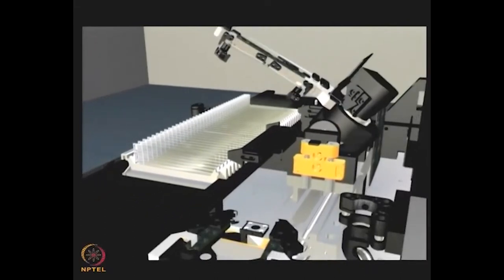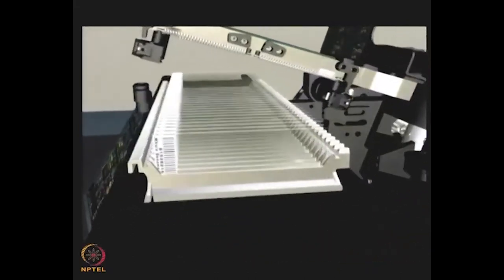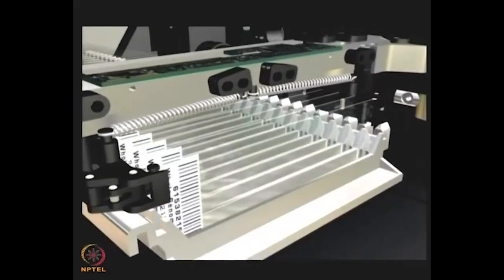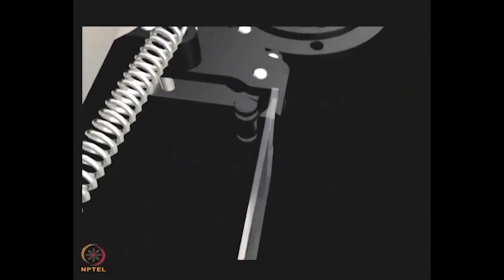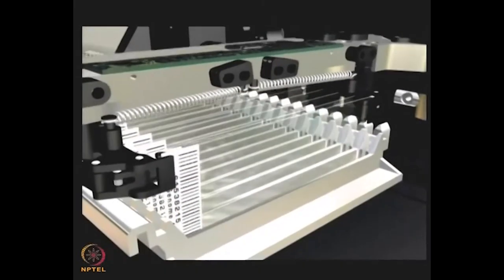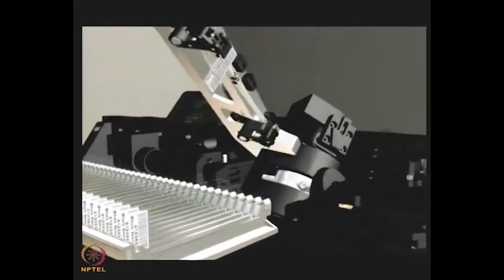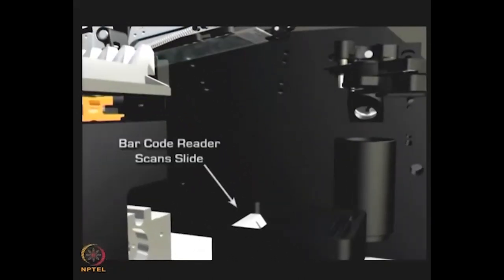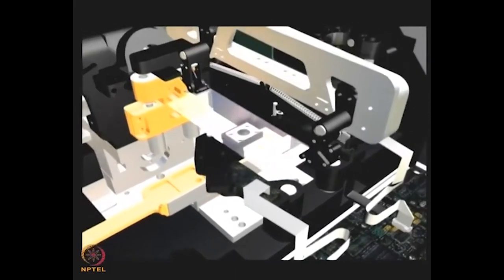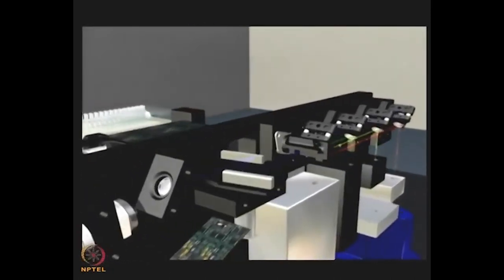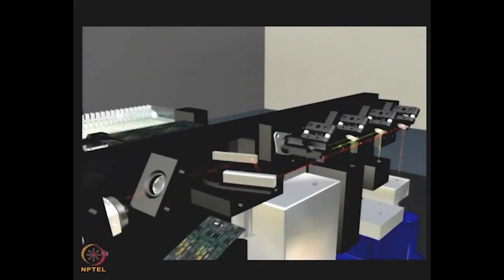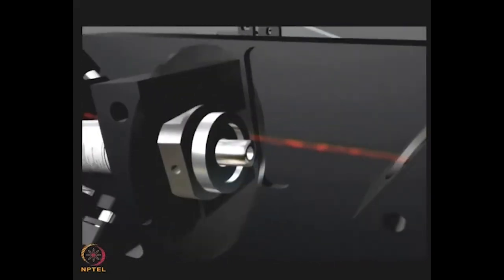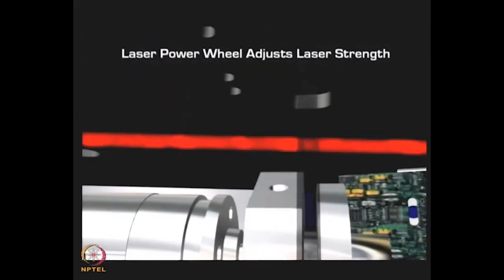Using the defined scanning parameters, the precision robot arm leaps into action and moves to the first slide. Our unique never-let-go grippers securely clamp the slide and carry it to the scanning area. A barcode reader records the barcode, and then the slide is positioned for scanning. The GenePix Autoloader 4200AL can be configured with up to 4 lasers. A neutral density filter wheel can be used to attenuate the laser power if necessary for especially bright samples.